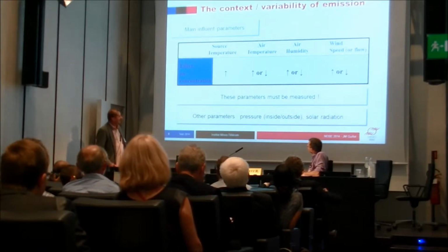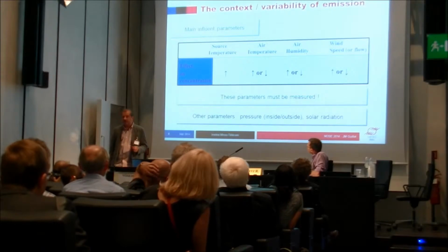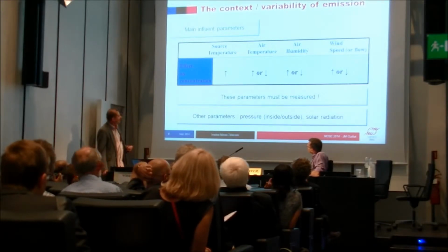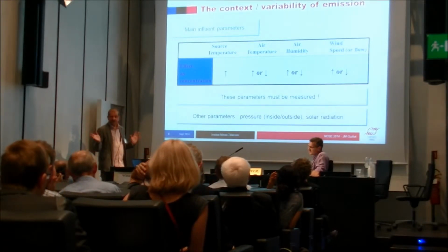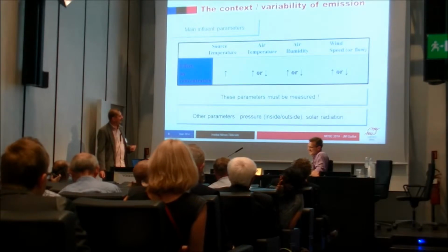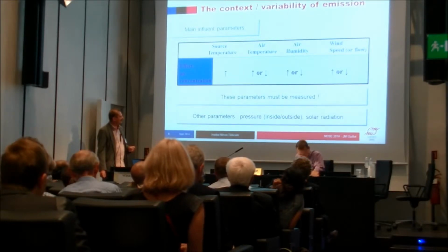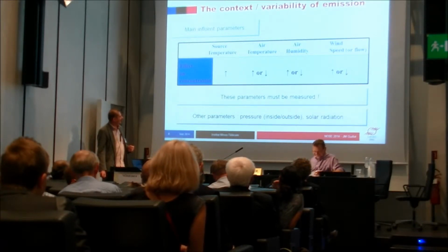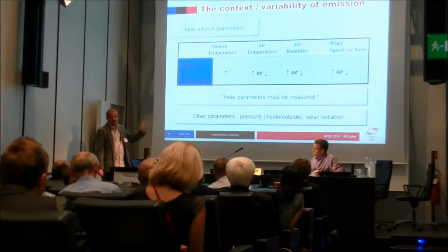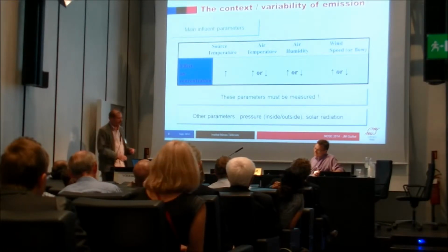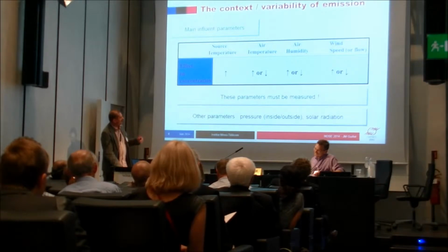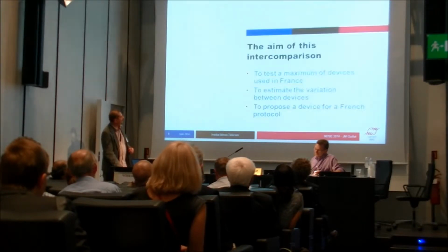We have also to consider other factors, typically the atmospheric pressure, to compare if there is a difference between inside and outside the chamber. If you have radiation, solar radiation, so if your device is increasing in temperature or not.